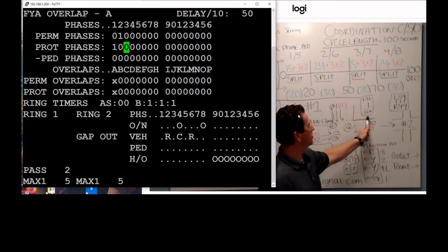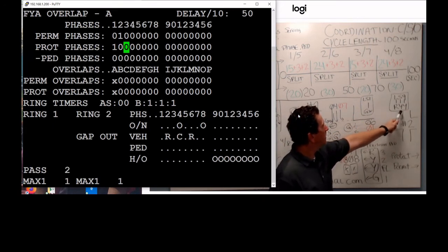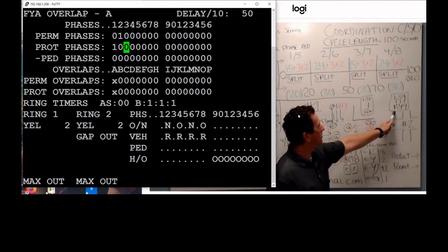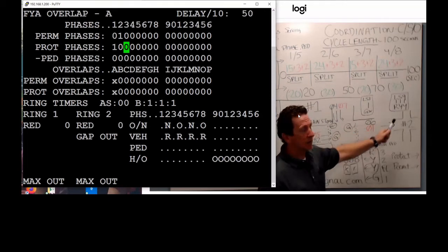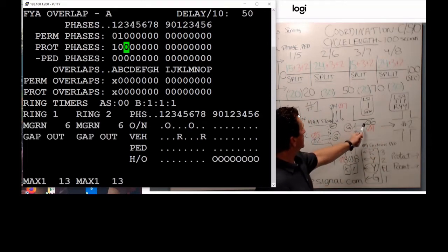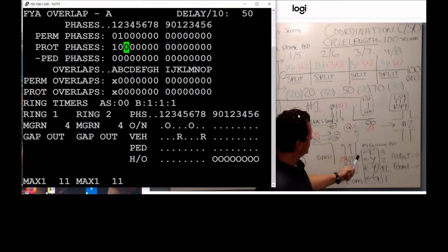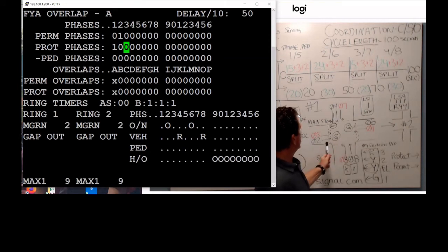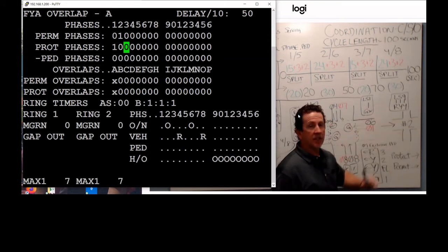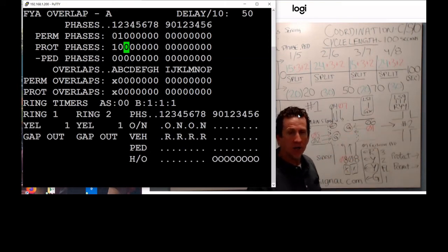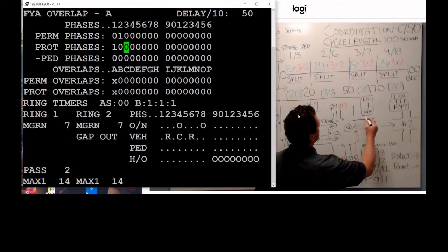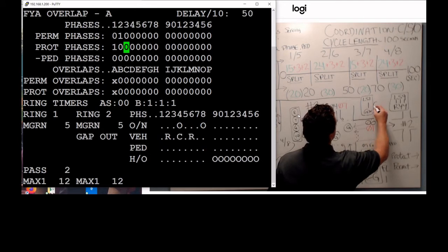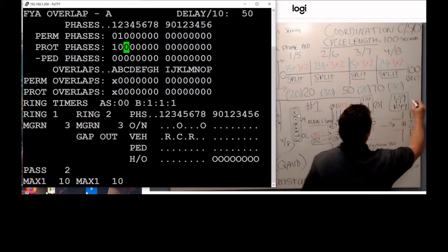So it would actually go to load switch 1, green, and then you would see it clear on load switch 9, yellow, load switch 9, red. And then once, I'm doing 2 and 1, I'll do it backwards. Once 2 comes on, you would then see the yellow on 9 start to flash. This is referred to as phase 1.